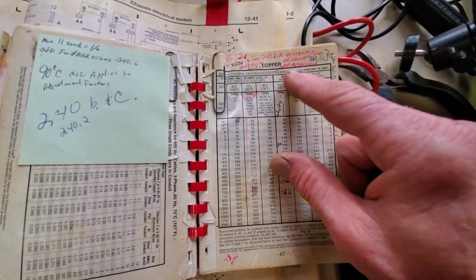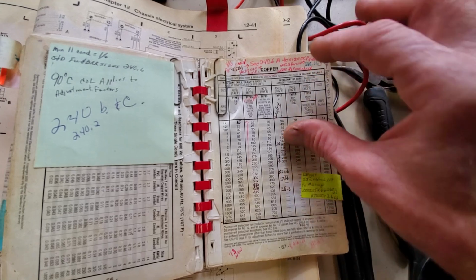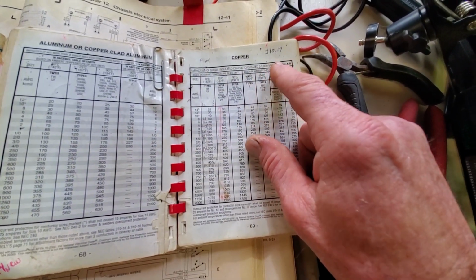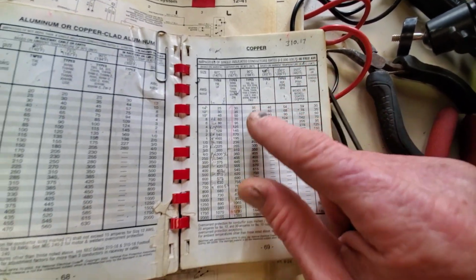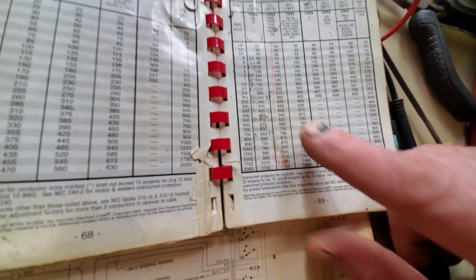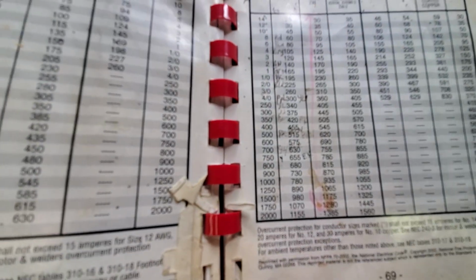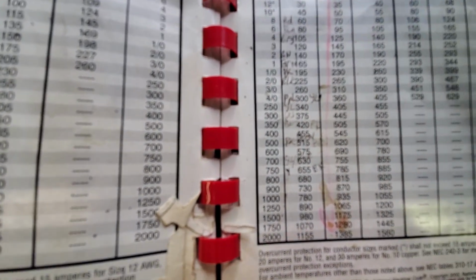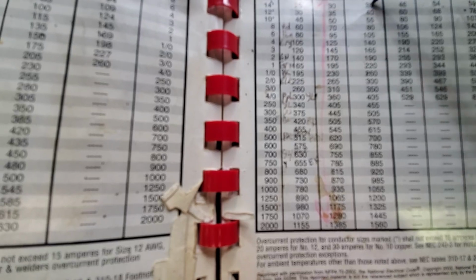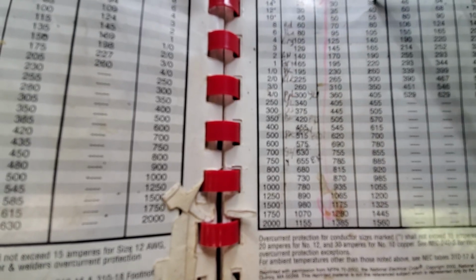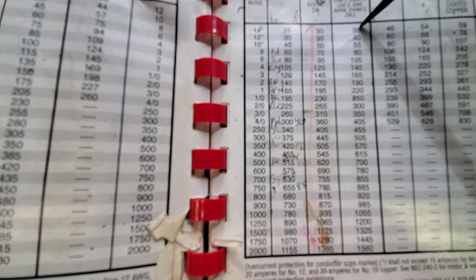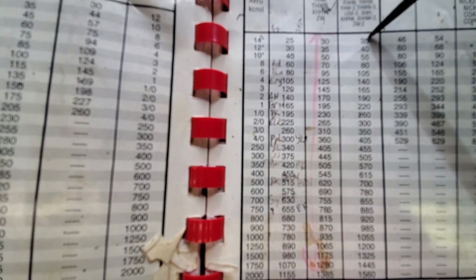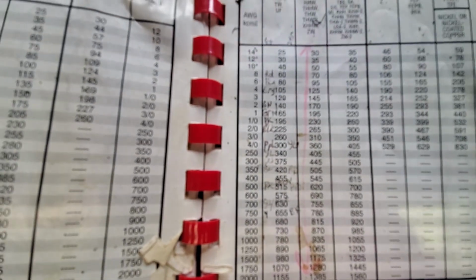You could use this in cable tray or raceway. I think for automotive applications they go by free-air ratings for wiring - for instance, a 90 degree C rating on 14 gauge wire is good for 35 amps. I would never do that, but hey, it's the code.